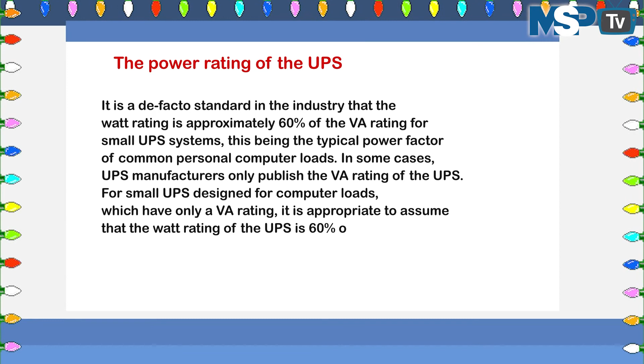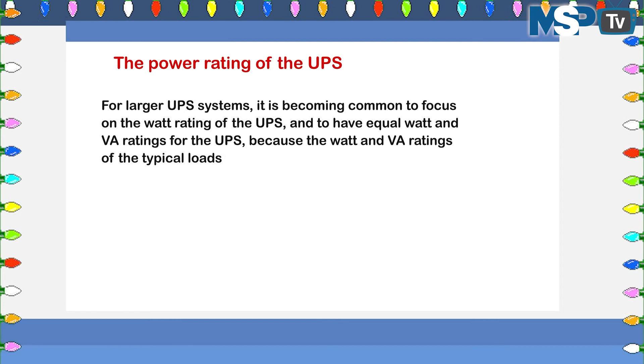In some cases, like small UPS designed for computer loads, UPS manufacturers only publish the VA ratings for the UPS. It is appropriate to assume that the watt rating of the UPS is 60% of the published VA rating. For larger UPS systems, it is becoming common to focus on the watt rating of the UPS and to have equal watt and VA ratings for the UPS, because the watt and VA ratings of the typical loads are equal. Now, with an example, let us see where a sizing problem can occur.